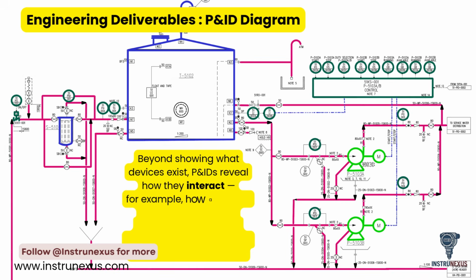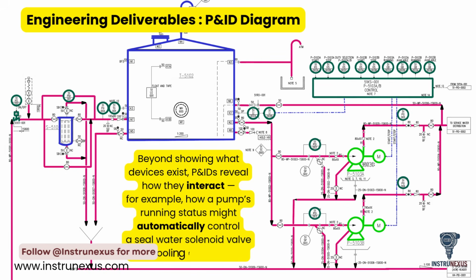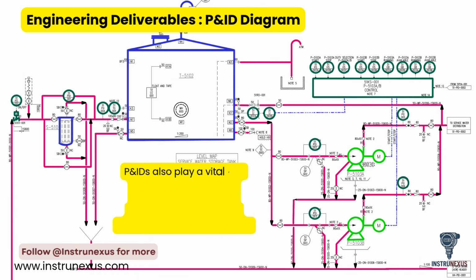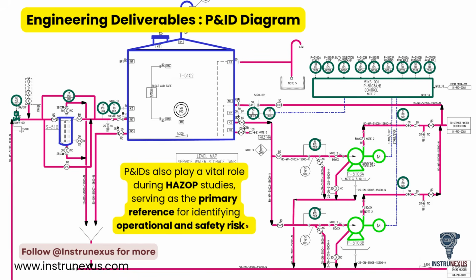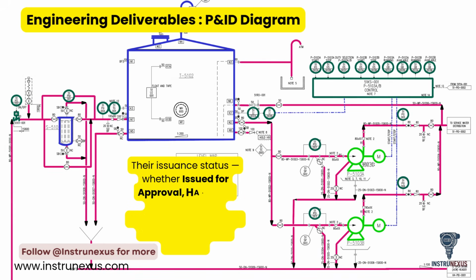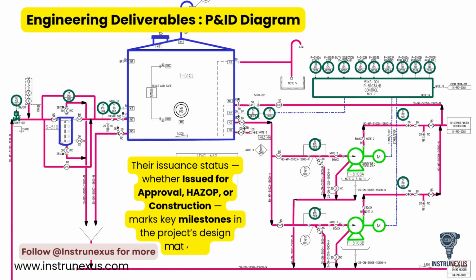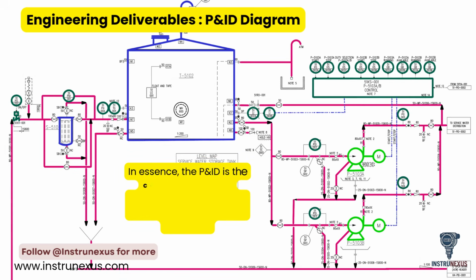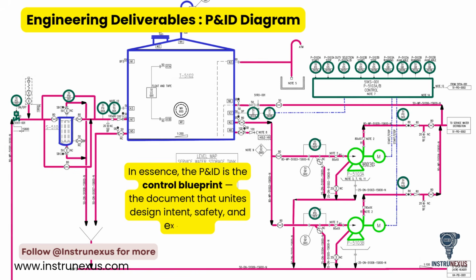For example, how a pump's running status might automatically control a seal water solenoid valve or a cooling fan interlock. P&IDs also play a vital role during HAZOP studies, serving as the primary reference for identifying operational and safety risks. Their issuance status, whether issued for approval, HAZOP, or construction, marks key milestones in the project's design maturity. In essence, the P&ID is the control blueprint, the document that unites design intent, safety, and execution.